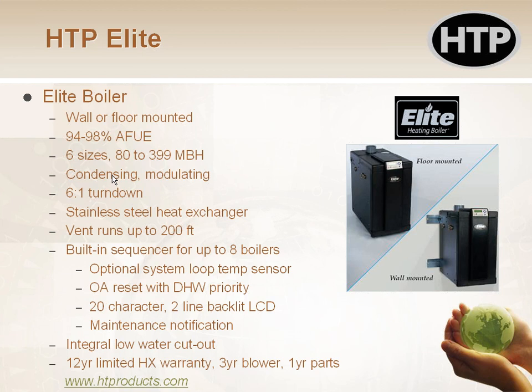So the bigger the turn down, the better it is for me to be able to handle smaller loads. Or if I have smaller zones and only one zone's calling, I'm better capable of handling that. It has the same stainless steel heat exchanger that the Munchkin Contender has. One big difference is vent runs. The old Munchkins only went up to 85 feet. The Elite can go up to 200 feet on the vent run. That's 200 equivalent feet, so that's pretty long. That certainly takes care of any residential situation and most light commercial projects.